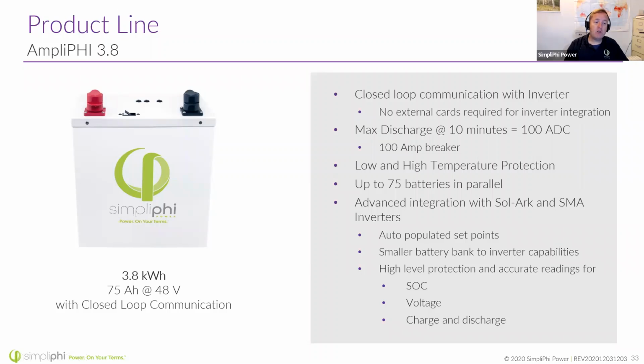This closed loop communication does a few things. One, it can auto-populate set points in the equipment you're using. Right now we're compatible with Sol-Ark and SMA, so it saves you time having to program every set point into that Sol-Ark. It also offers higher level protections, because if you go into that inverter and set something wrong, the battery will tell the inverter no, that's not right, go ahead and revert to a setting that's going to protect me.